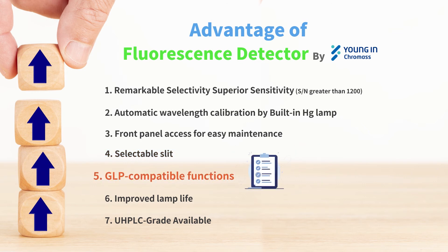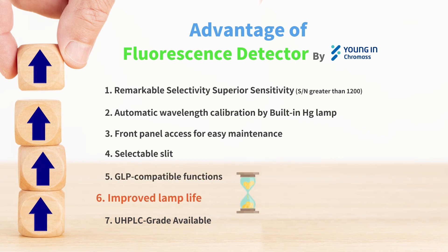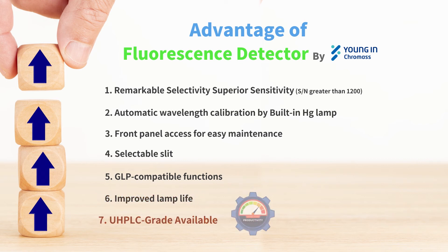And the GLP compatibility function is available for lamp energy, lamp ignition time, number of ignitions, date of last lamp replacement, as well as wavelength accuracy. The newly adopted xenon lamp ensures long life of the light source to reduce running costs. Finally, the UHPLC grade FLD is also available for better resolution and faster analysis time.